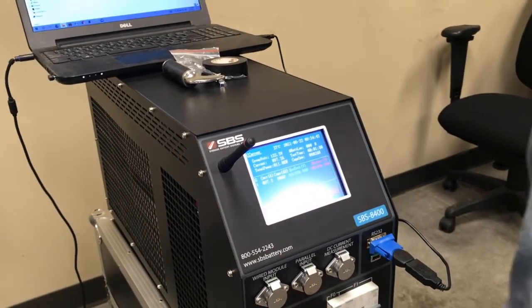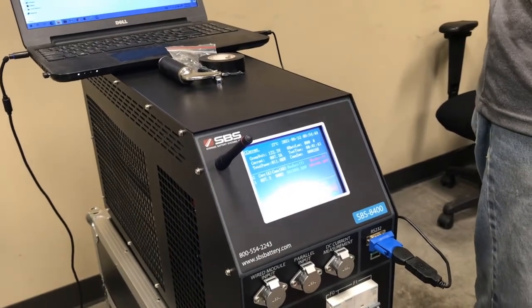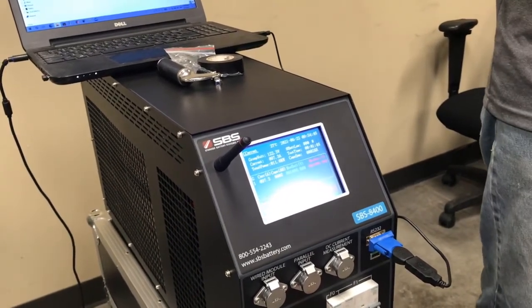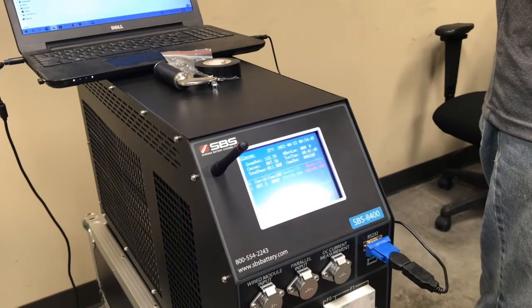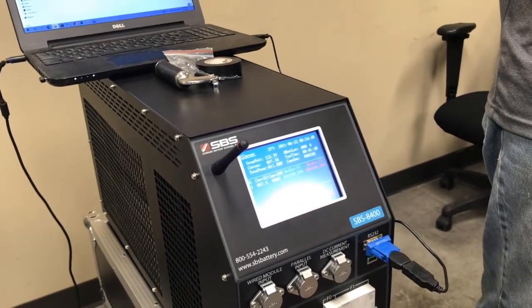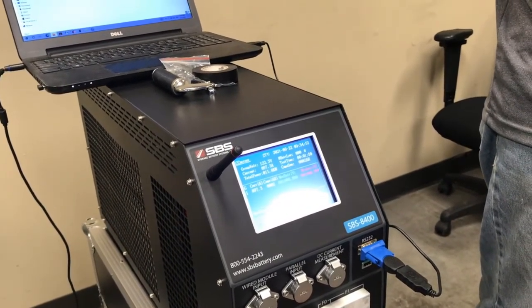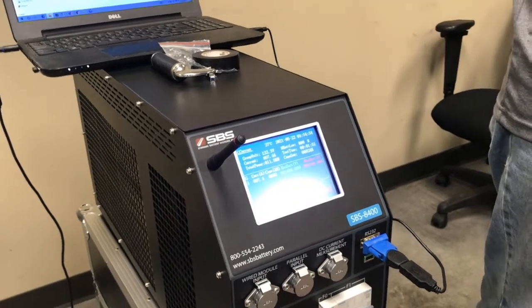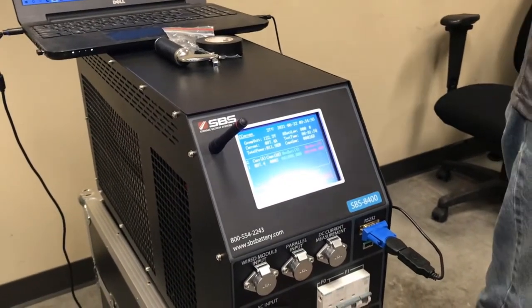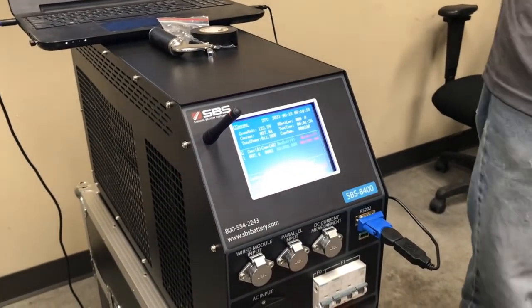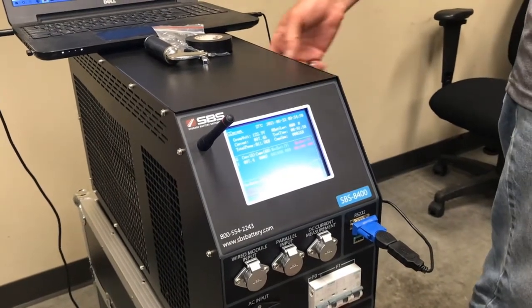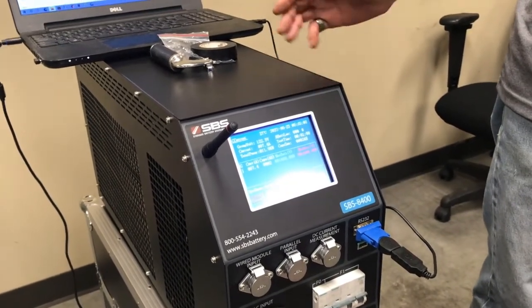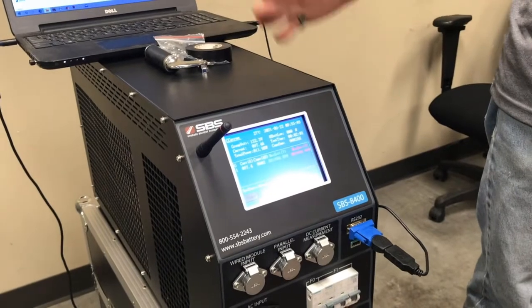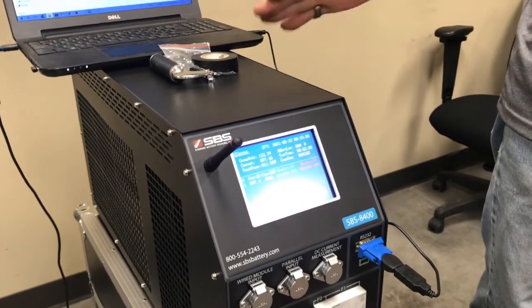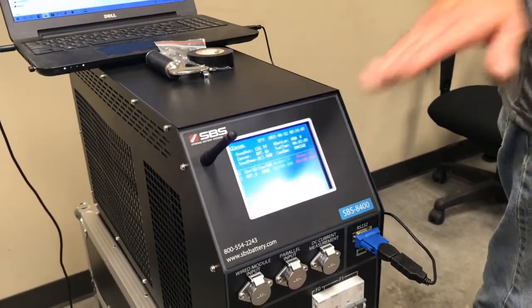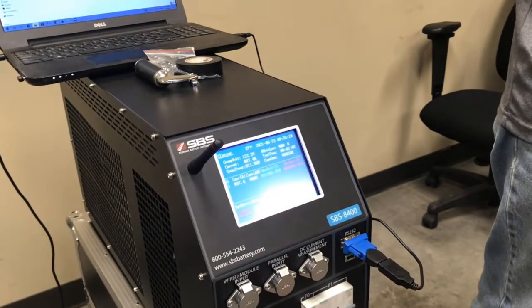The unit has 4 automatic built-in shutdowns. If it reaches test time, test capacity, group low voltage, or number of cell low voltages times the number of low cells, it will automatically terminate the test. It has heat sink thermocouple or thermistors. So if the heat sinks reach 40 degrees Celsius, it'll give me a high temperature alarm and it'll automatically stop the test on the overtemperature.